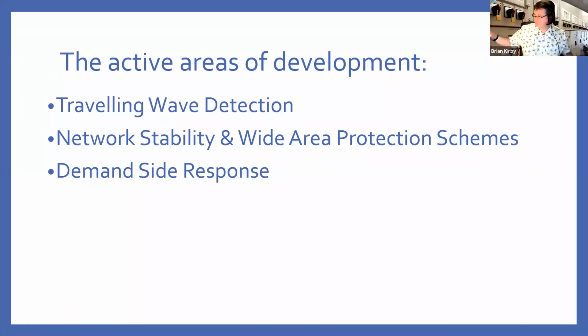Okay, so there are some other, again, bespoke protection methods used in DC protection, but those are the primary functions that are used universally to protect the scheme, because it's all embedded within the converter station. So if we look now at the sort of active development in protection these days, one is traveling wave detection, and this is an interesting one in that it has applications on AC systems and on DC systems, because it gives you high speed detection of faults, and also allows you to locate them, which is going to be important when you're performing multi-terminal DC networks.